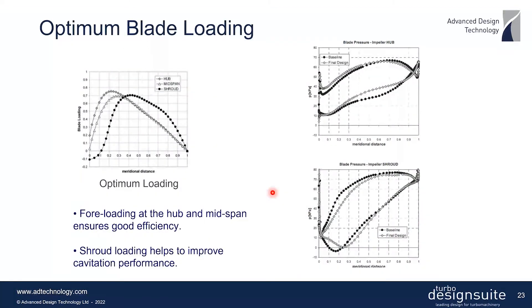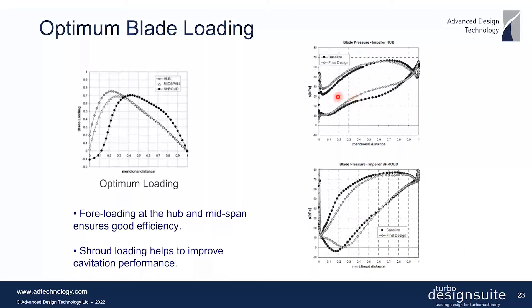To address this, they developed a novel loading distribution: at the hub and mid-span they use a front-loaded distribution, but at the shroud they unload the first 10% and then maintain an almost front-loaded distribution after that. The effect on surface static pressure shows that this removes the dip that was going below vapor pressure and causing cavitation at the shroud. The front loading at hub and mid-span is important for this mixed flow impeller as it rapidly diffuses the flow, ensuring low profile losses and relatively high efficiency.